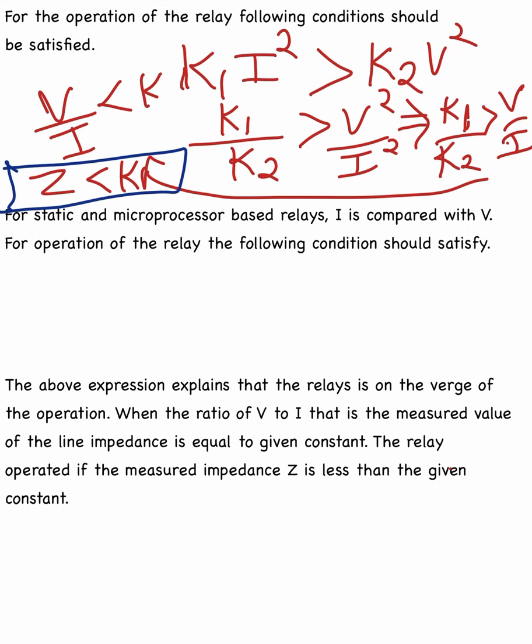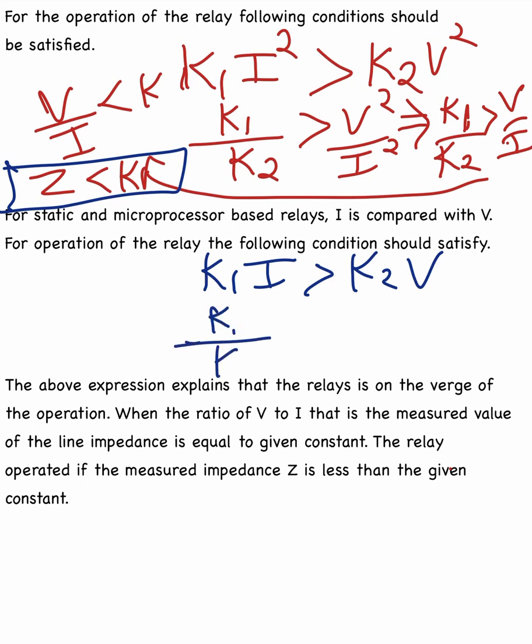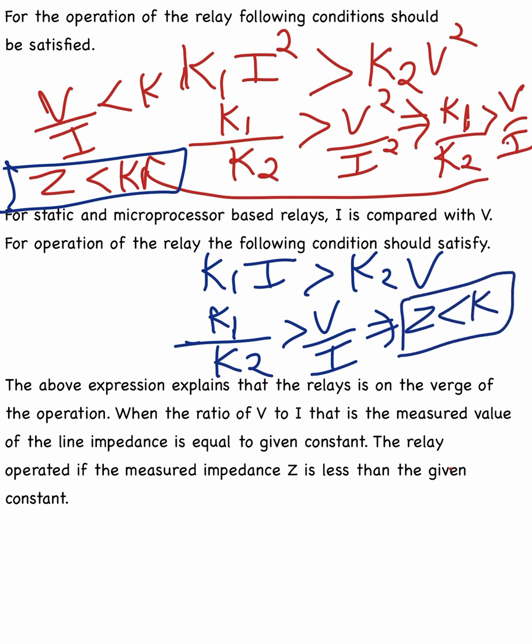For static and microprocessor-based relays, current I is compared with voltage V, and the operating condition is k1·I > k2·V, giving Z < k. The relay is on the verge of operation when the ratio V/I — the measured line impedance — equals the given constant k. The relay operates if the measured impedance Z is less than the given constant k.